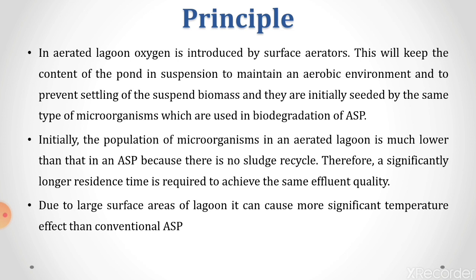Principle: in aerated lagoons, oxygen is introduced by the surface aerator. This will help the content of the pond in suspension to maintain the aerobic environment and to prevent settling of the suspended biomass, and they are initially seeded by the same type of microorganism which are used in the biodegradation of ASP. So it is the same as an ASP, where to have an initial build up of the microorganism, the initial seeding or the addition of the microorganism is carried out.